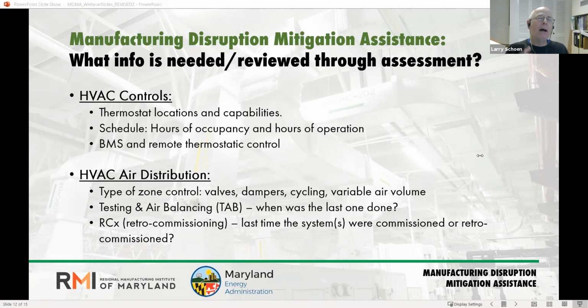And I mentioned earlier about measuring air that is coming in from the outdoors and going to different places, whether it's an exhaust and makeup system for a dedicated process or whether it's a code-required ventilation system. It's important to know and measure that. ASHRAE now recommends measuring amounts of outdoor air at least every 5 years. That's not a legal requirement. That's an ASHRAE recommendation in its standard. But it's a good idea, particularly in these times. And so that gets into the larger issue of retro-commissioning.